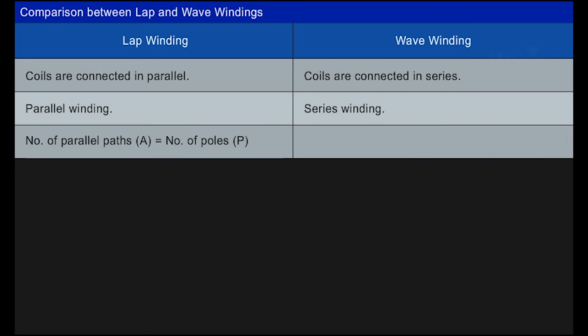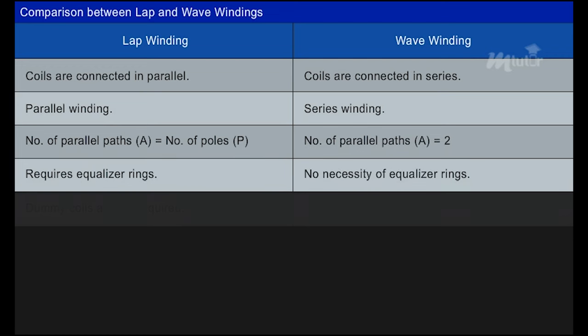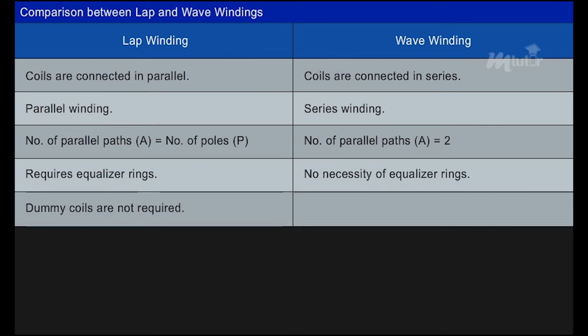In lap winding, the number of parallel paths A is equal to the number of poles P, whereas in wave winding the number of parallel paths A is equal to 2. Lap windings require equalizer rings for better commutation, but wave windings do not. Dummy coils are not required in lap windings but may be used in wave windings.